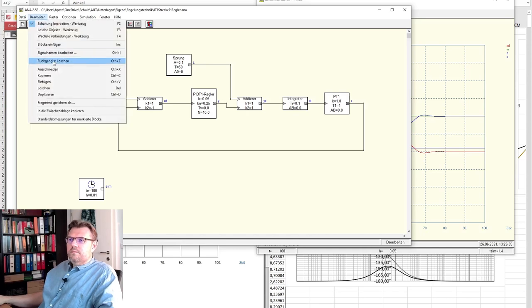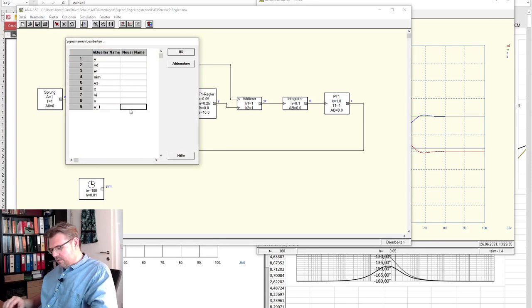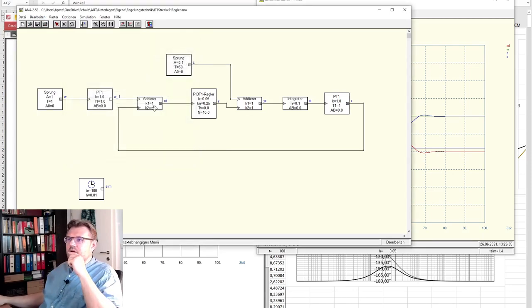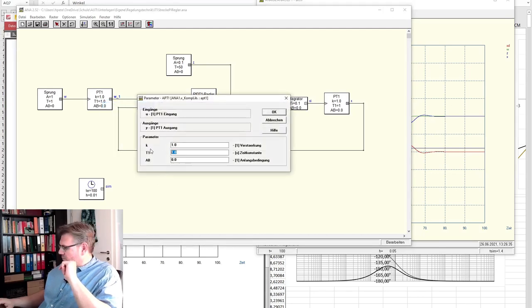This I want to rename. This shall not be Y1. This is W1, because it's the wanted value. And I want to have it also in my oscilloscope. I only have to select the filter time, and as filter time, I need the same time constant as in the controller.